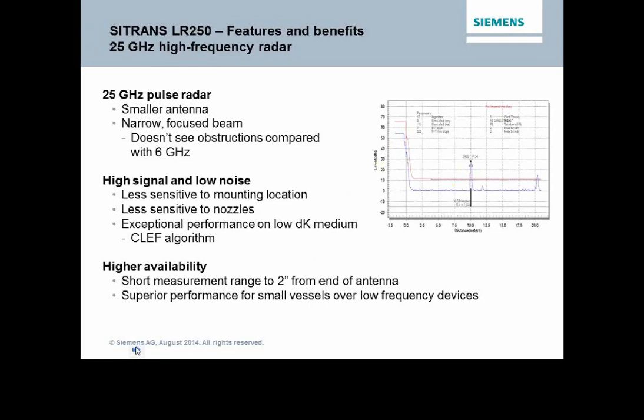So we have higher availability. What becomes important is how short my measurement range is, or my blanking distance. When it comes to ultrasonics, the blanking distance is a minimum of a foot because I'm dealing with the speed of sound, and the unit itself rings and has to actually come back to rest. And that resting time forces there to be a greater blanking range. With radar, that blanking range is much smaller. The general rule is twice the flange diameter.